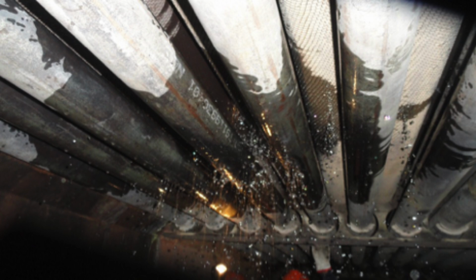So this is the bottom side of tubes of the bank heat exchanger, and you can see, unfortunately the picture is not that clear, I think, but there's water running all the way down here. And these actually failed every 6 months from the install. It was a new plant that they installed, and every 6 months they had failure. And when they analyzed the corrosion products, they also found chlorides, and therefore they said it was the chlorides and the water treatment. And there were quite a few stories given for the reason for these failures.